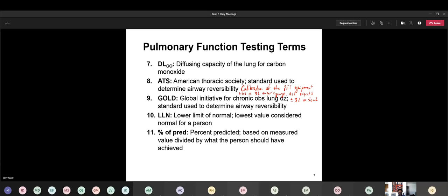I mean, there's other standards in there as well, but that's one of the main things: your machine has to be able to pass calibration. If you got a busy lab, you've got to do this calibration multiple times throughout the day. You can't just do it in the morning and continue to do all these patients and expect everything to still be okay. You want to be assured that the numbers you're getting in your test results are pretty close and pretty accurate. And that's the whole point of calibration. It's all a quality assurance kind of thing.